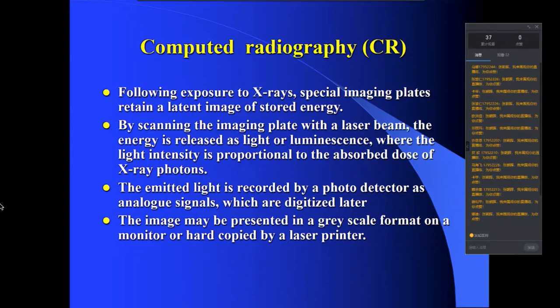And seeing all these shortcomings of conventional film-based radiography, people developed computed radiography. In computed radiography, following exposure to X-rays, special imaging plates are used to retain a latent image of stored energy. By scanning the imaging plate with a laser beam, the energy is released as light or luminescence, where the light intensity is proportional to the absorbed dose of X-ray photons.